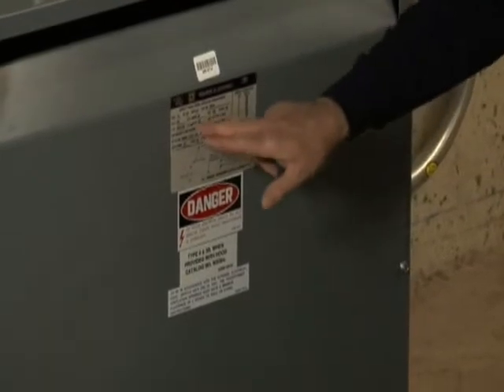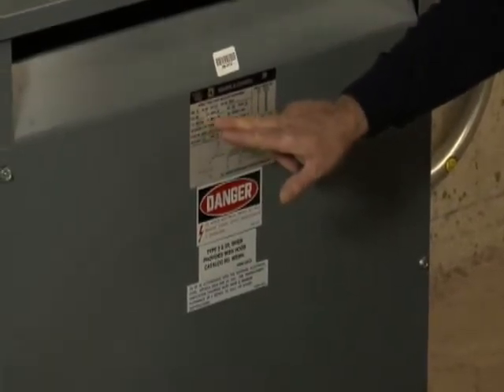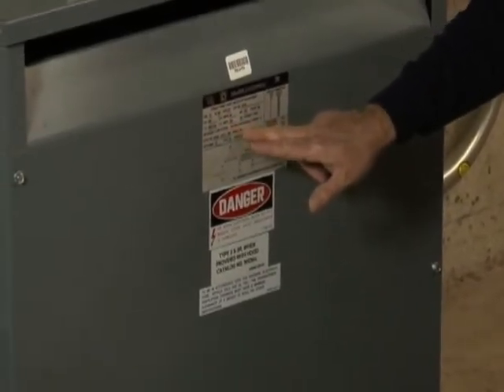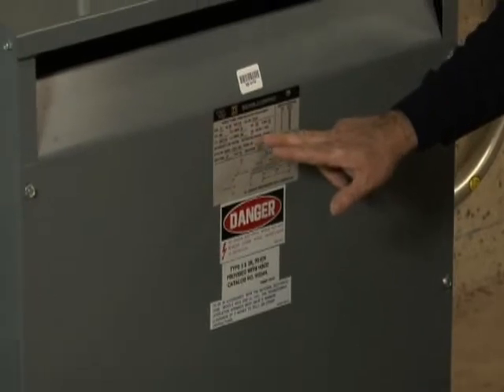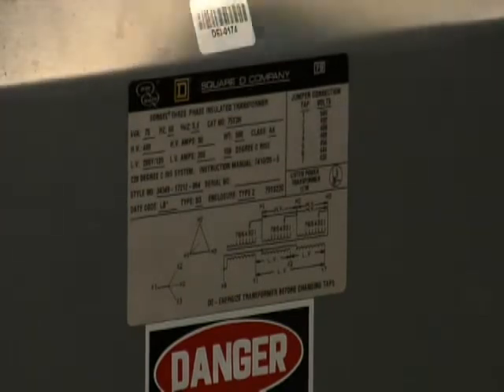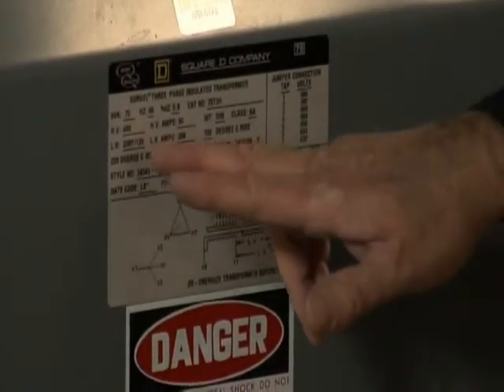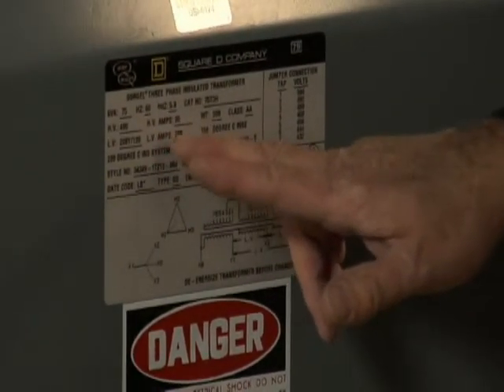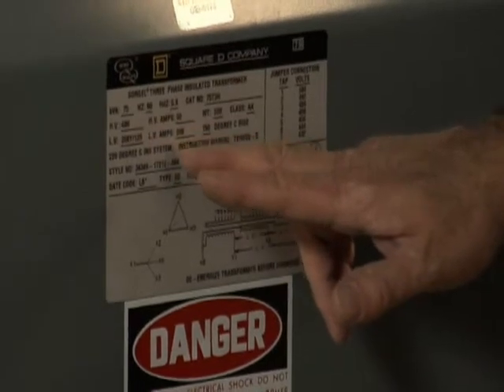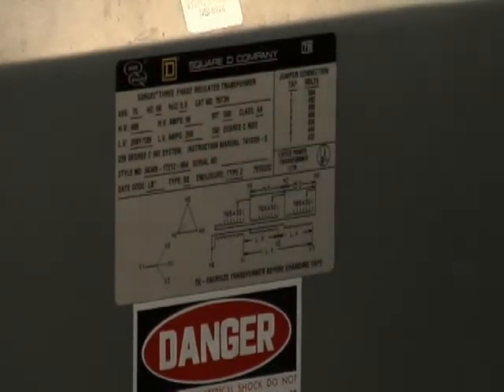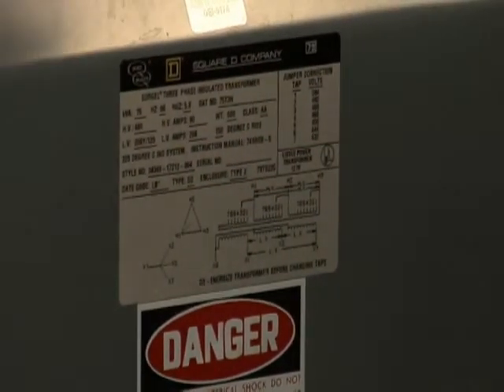Before I start, I always check the nameplate for the transformer ratings. Be sure to record kVA and the voltage and current ratings for both the primary and secondary sides. Record the ambient temperature and temperature rise information, and note any required installation clearance requirements, usually found on a separate label. All of this data will be used later.